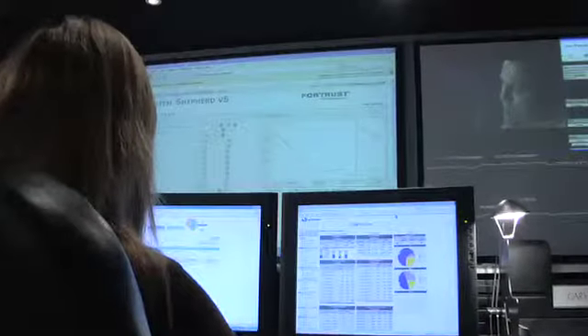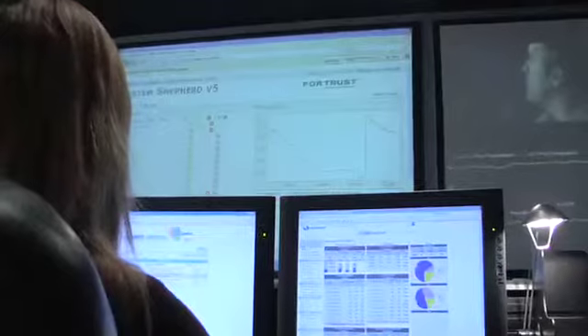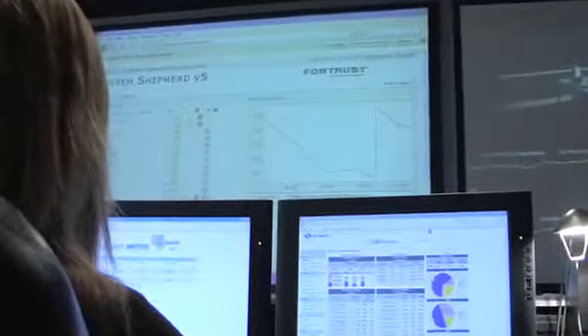Good, good. Can you tell me a bit about the monitoring systems you have in place? Yes, we have a monitoring and control system that monitors various points of the facility. We monitor everything from temperature and humidity throughout the facility, to power consumption and distribution all the way down to the breaker level, power distribution units, static transfer switches, and all fire and life safety systems, all reported through this monitoring system.